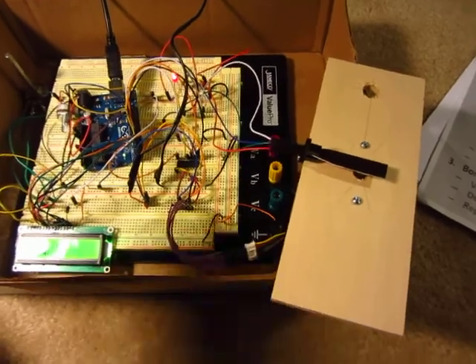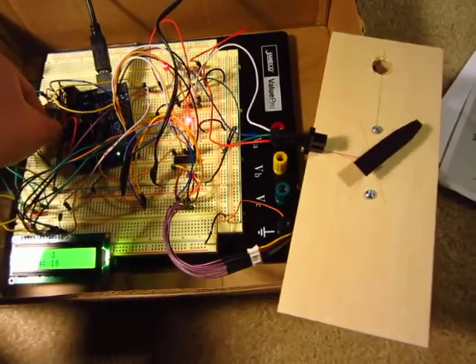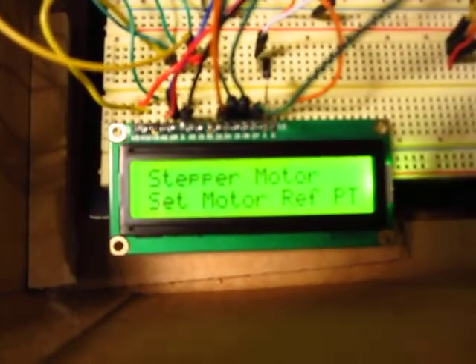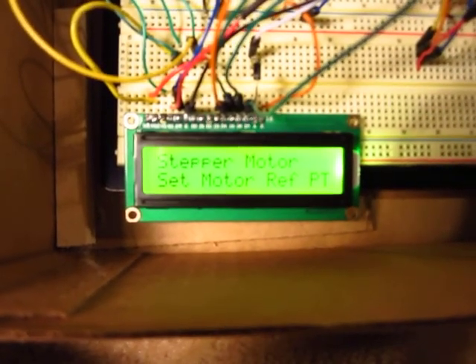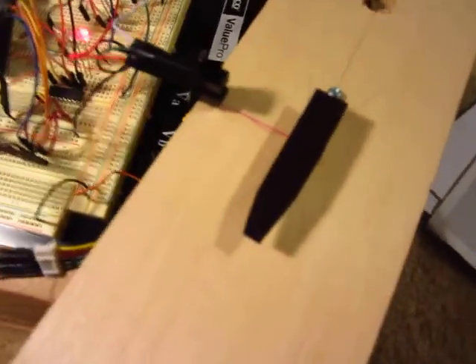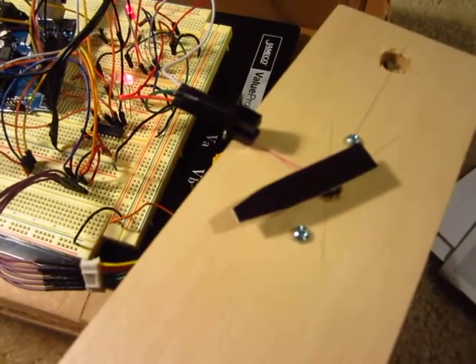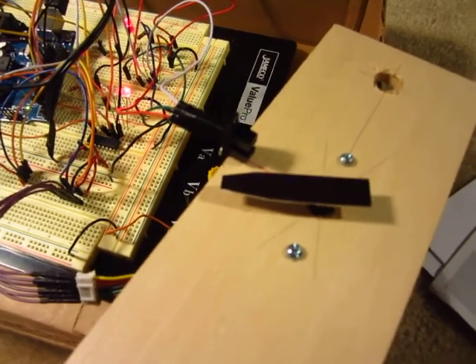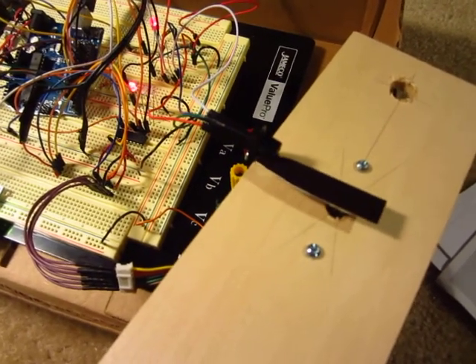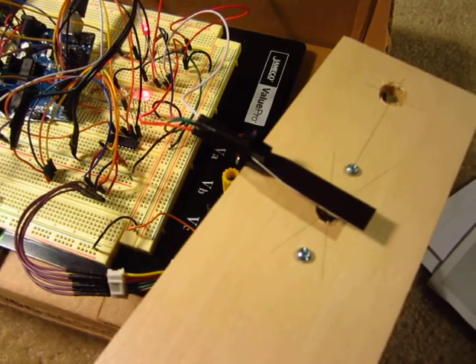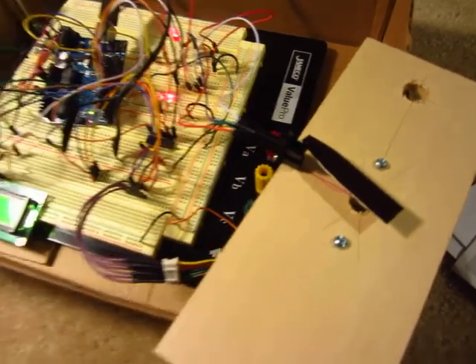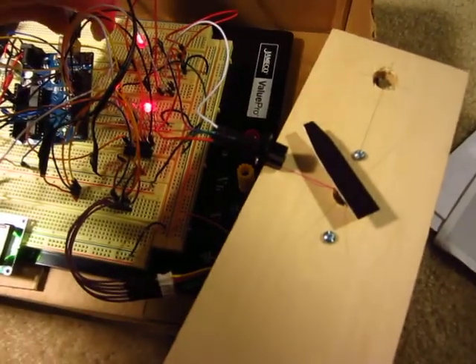To give you a better idea, we can slow it down to around 1 RPM and reset it. Here you can see it's setting the motor reference point where it's going clockwise until it finds the optocoupler. And then it will start going 12 steps.